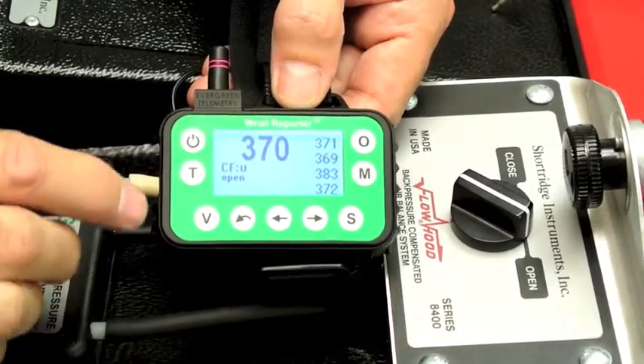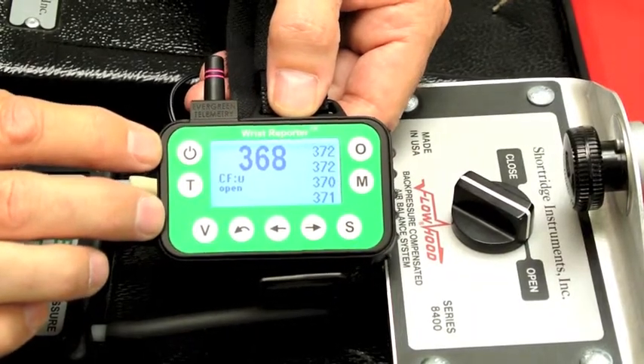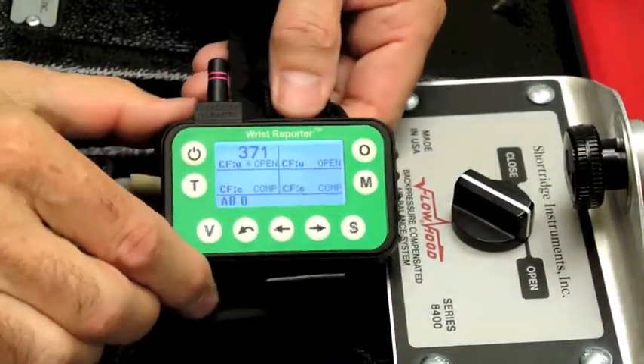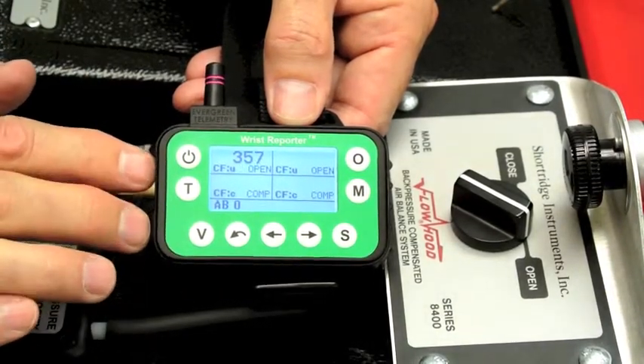There is one display view screen of the wrist reporter that deals with taking back pressure compensation readings, and one only. And that one is this split screen view. This is the screen to use when back pressure compensation readings are being made.